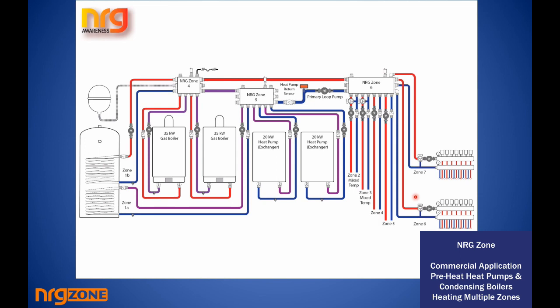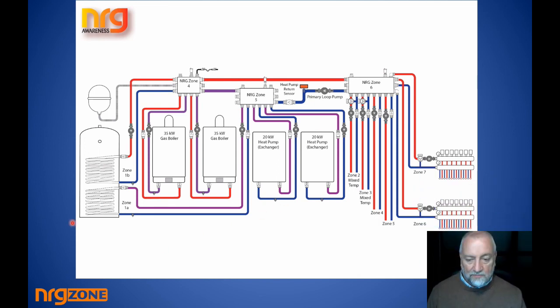What have we got? So we have heat pumps that can do preheating on the hot water. We have gas boilers that can preheat the hot water, or can heat at full temperature. But if we ever turn on this shunt pump, and that will turn on very simply because one of those zones here is calling, the coldest water coming back from the heating system will be put through the bottom chamber of the NRG 5. It'll be taken by the heat pumps and put up to, let's say, 45 degrees.